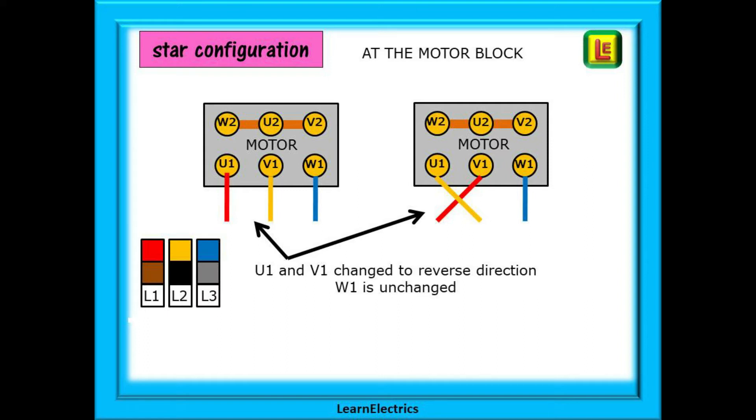You may be working with the brown black gray system of cable colors, or you may have all black where they are marked L1 L2 L3. It makes no difference, just swap over any two wires and the job is done.